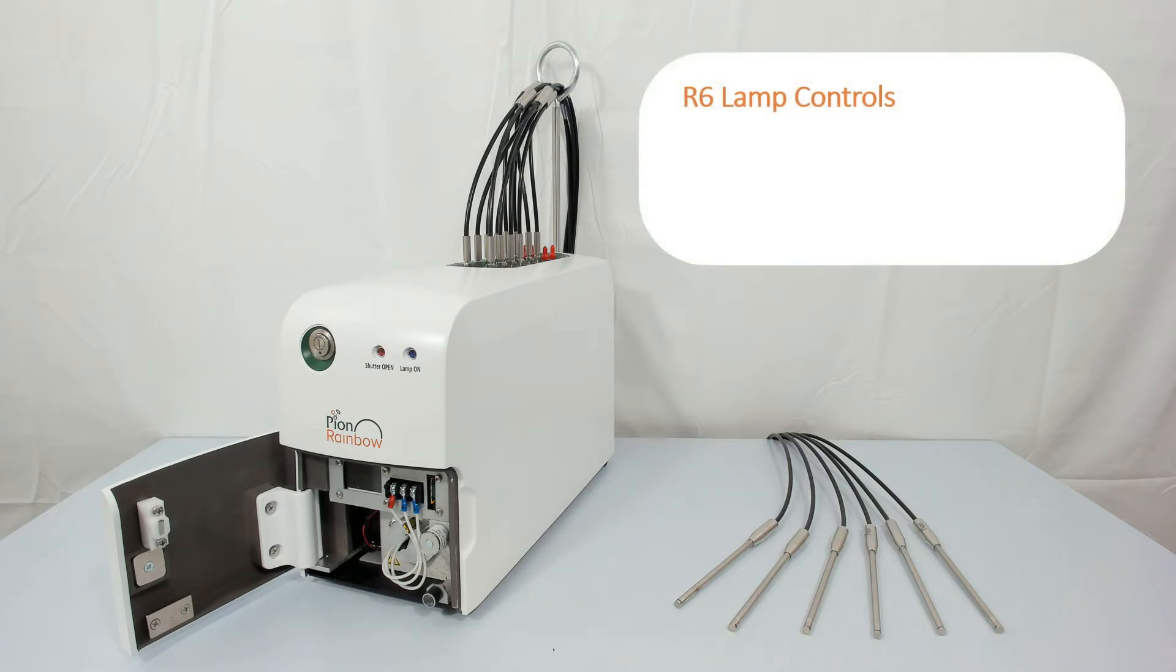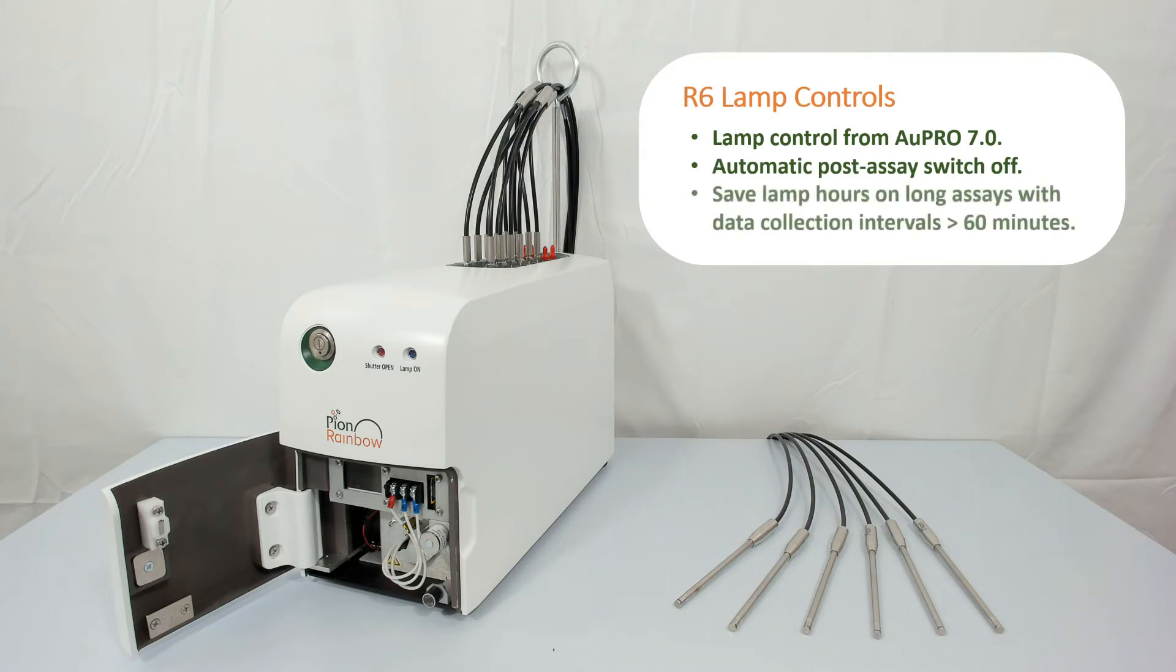The revised lamp hardware also allows the AuPRO software direct control of the lamp itself, enabling automatic shut-off of the lamp post-assay, and even mid-assay during sequences with a point collection interval of longer than one hour, lending to a significantly improved lamp lifetime.